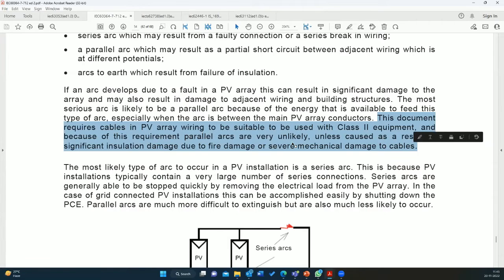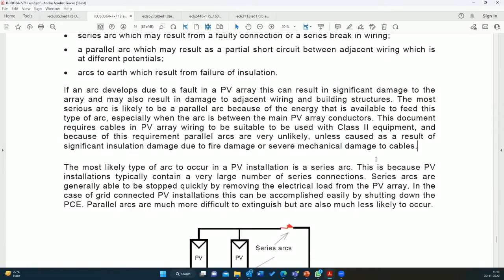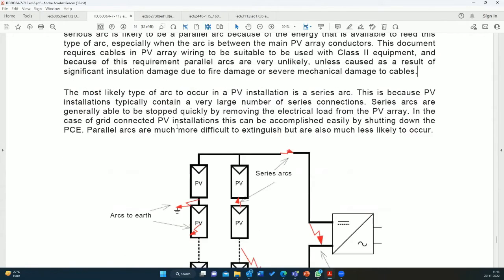If we read it in another way, if you use class 2 wiring or class 2 equipment, the parallel arc is unlikely. That means if you compromise it, they are likely, unless caused as a result of significant insulation damage due to fire damage and severe mechanical damage to cables. The most likely type of arc to occur in a PV installation is a series arc. This is because PV installations typically contain a very large number of series connections.